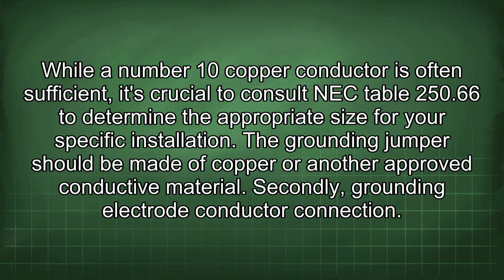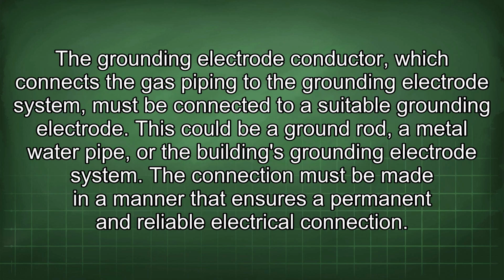Secondly, grounding electrode conductor connection. The grounding electrode conductor, which connects gas piping to the grounding electrode system, must be connected to a suitable grounding electrode. This could be a ground rod, a metal water pipe, or the building's grounding electrode system. The connection must be made in a manner that ensures a permanent and reliable electrical connection.